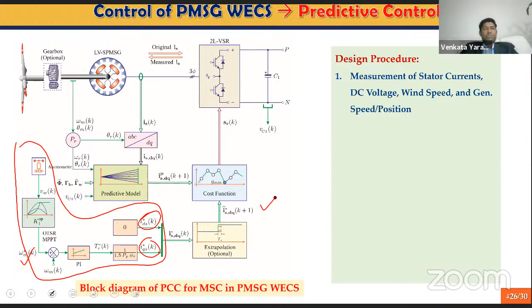So we see the design procedure. First one is that we measure the stator currents, DC link voltage, wind speed, and generator speed and position. Next, we estimate the rotor angle, which is theta R. And then we calculate the reference stator currents, similar to the linear control. And then we extrapolate the reference currents to the K+1 state. And then we predict the future behavior of stator currents based on the available number of switching states in the converter. So for the two-level inverter, we got 8 possible switching states. So we get 8 predictions for the currents. And then we do the cost function minimization, and we see which switching state has the lowest error. And then we take that switching state and apply it to the inverter.